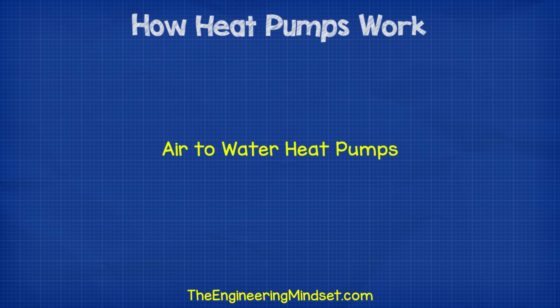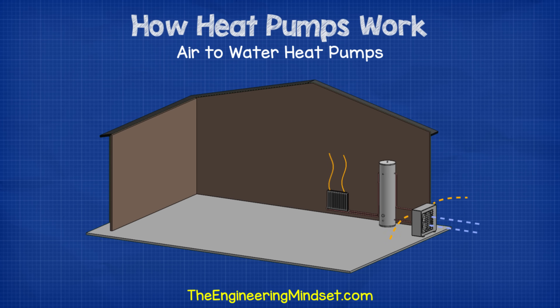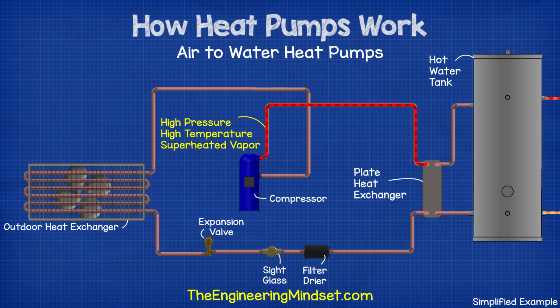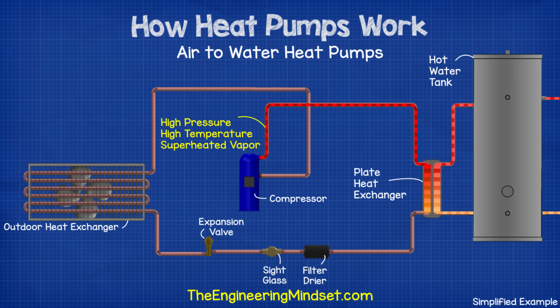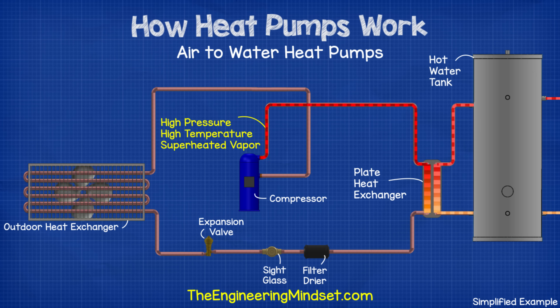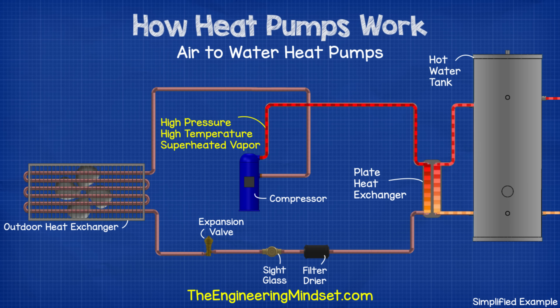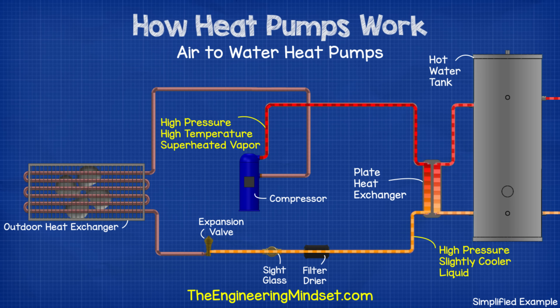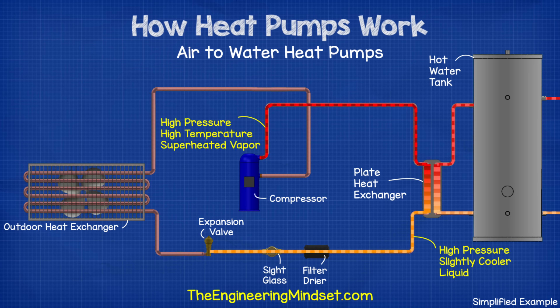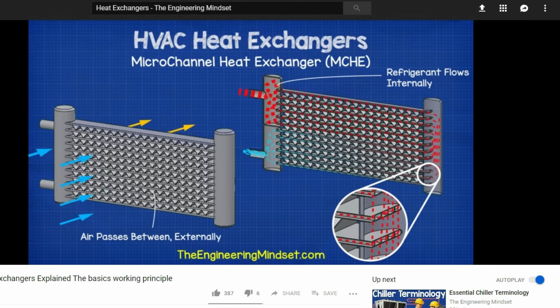Air to water heat pumps work in a very similar manner to air to air heat pumps, but without the reversing valve. The high pressure, high temperature vapor refrigerant leaves the compressor and heads into a plate heat exchanger. On the other side of the plate heat exchanger, water is being cycled through a hot water storage tank. Cool water enters the heat exchanger from the tank, and as it passes through, it absorbs heat from the hot refrigerant. The water then leaves at a much hotter temperature and flows back to the hot water storage tank to repeat the cycle. As the refrigerant gives up its heat to the water, it will condense, and it will leave the heat exchanger as a high pressure, lower temperature liquid. We've covered how heat exchangers work in our previous videos — links can be found in the video description below.